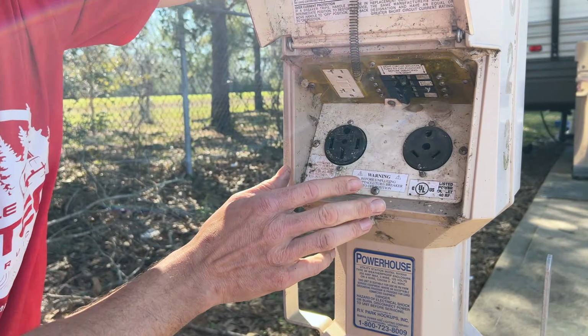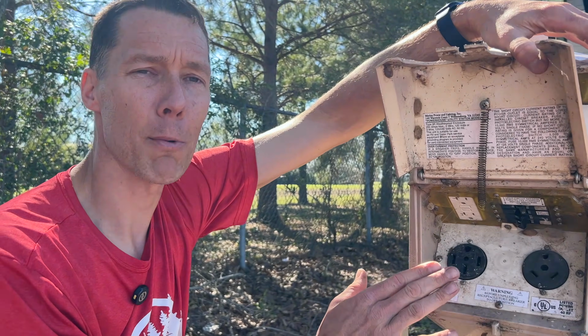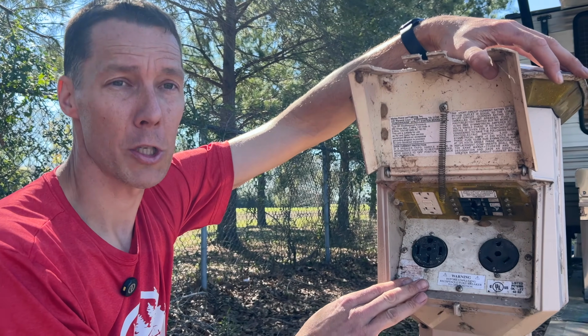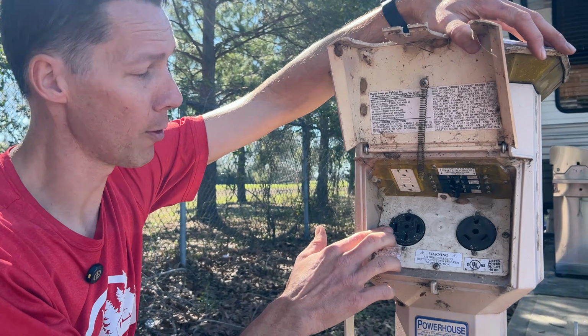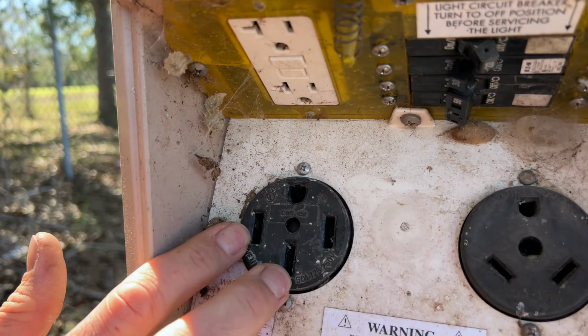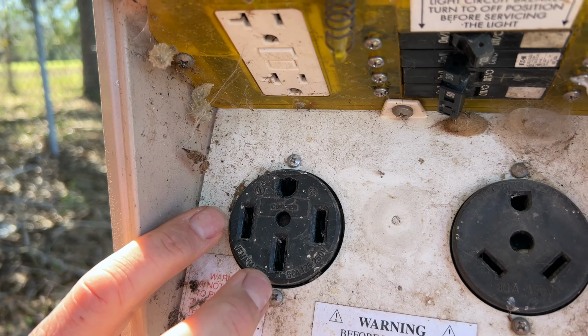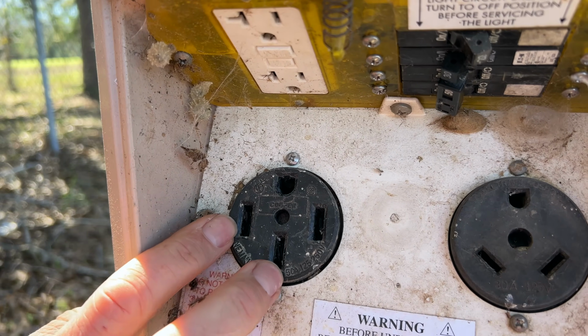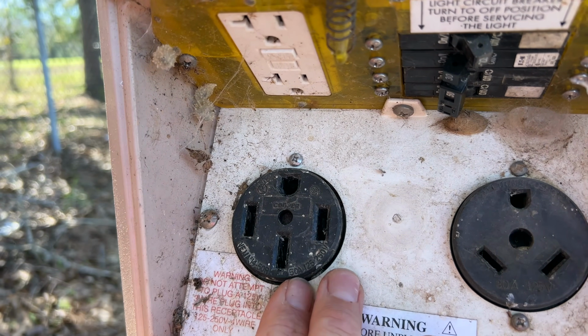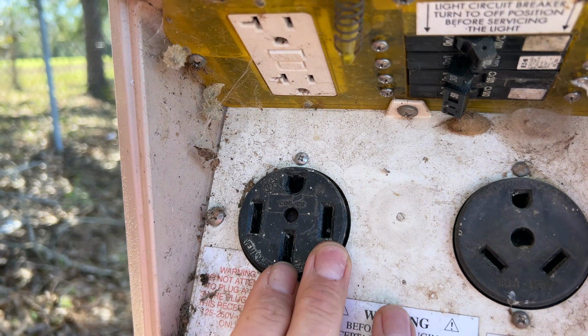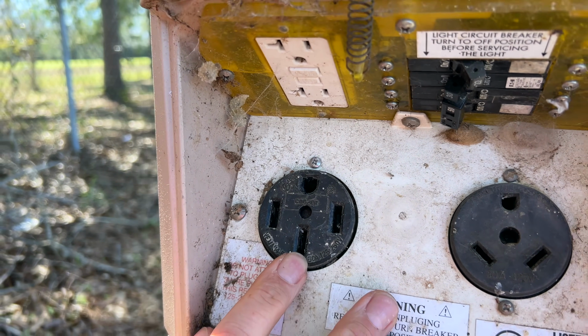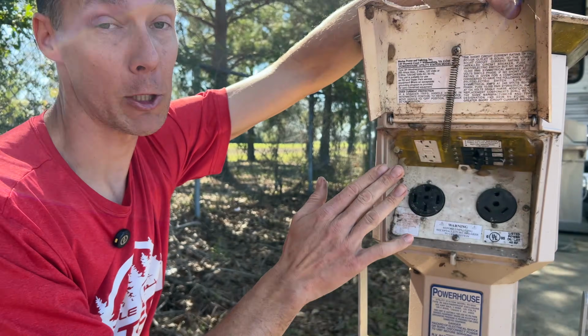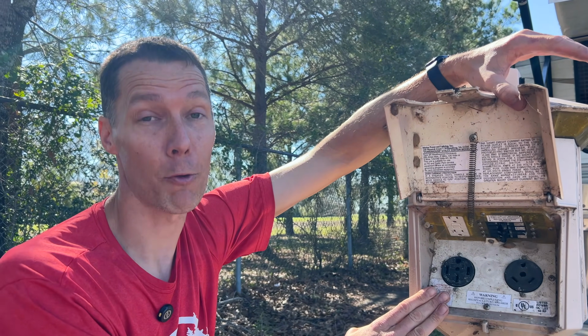The other thing you don't want to see is anything not around 120 volts. So let's say on our 50 amp plug, if we measured between hot and neutral on one side, let me say 180 volts between your hot and neutral, and the other side read 80 volts between your hot and neutral, that means you have a neutral issue inside of there. It needs to be checked out. That is not safe power for your RV.